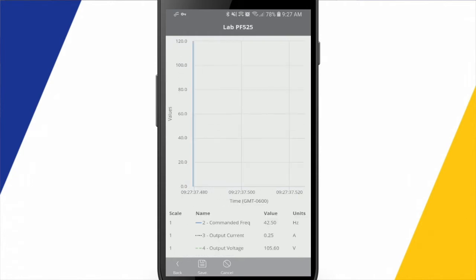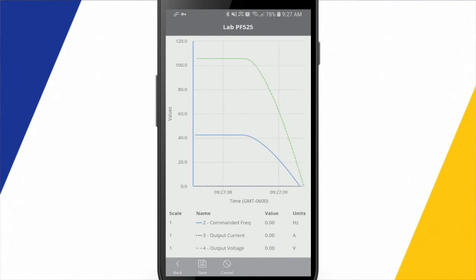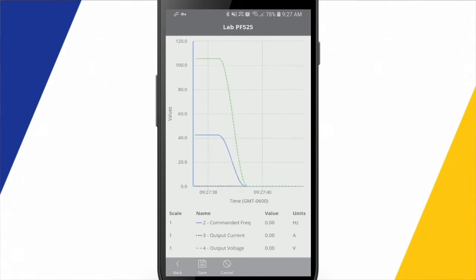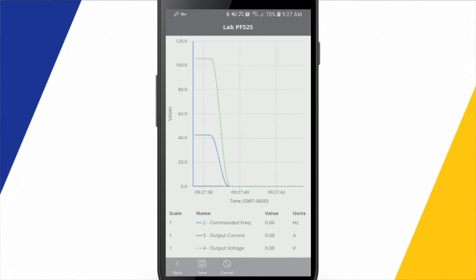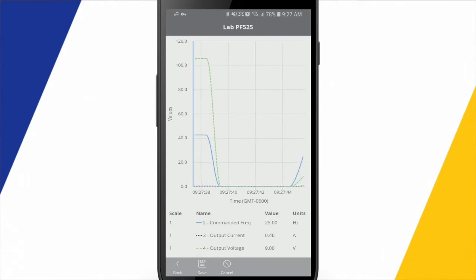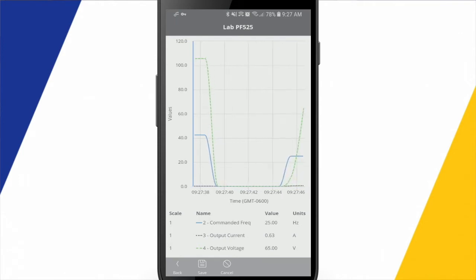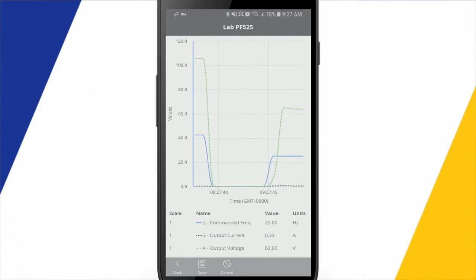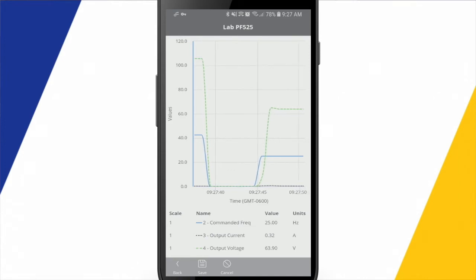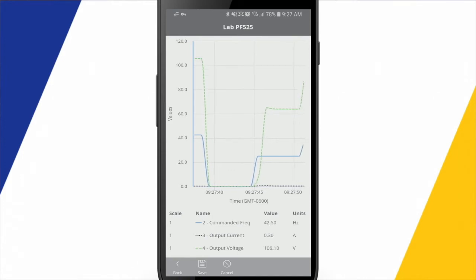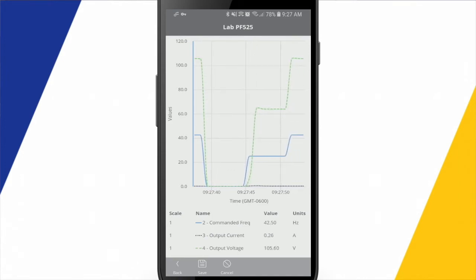So if I go next here, all right, so I can see that my trend is running, and I have a program set up in there to just ramp this drive up to 25 hertz, hold there for a few seconds, and then it goes up to 42.5 hertz.